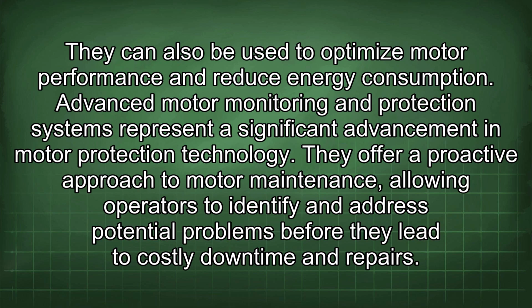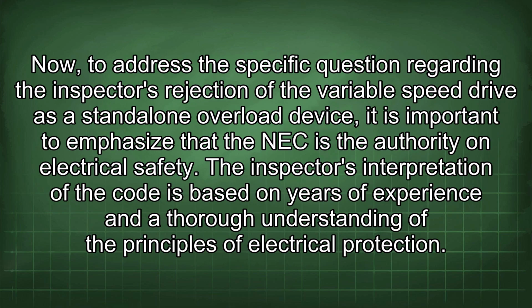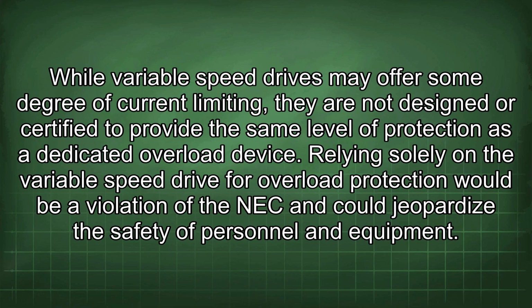Now, to address the specific question regarding the inspector's rejection of the variable speed drive as a standalone overload device, it is important to emphasize that the NEC is the authority on electrical safety. The inspector's interpretation of the code is based on years of experience and a thorough understanding of the principles of electrical protection. While variable speed drives may offer some degree of current limiting, they are not designed or certified to provide the same level of protection as a dedicated overload device. Relying solely on the variable speed drive for overload protection would be a violation of the NEC and could jeopardize the safety of personnel and equipment.